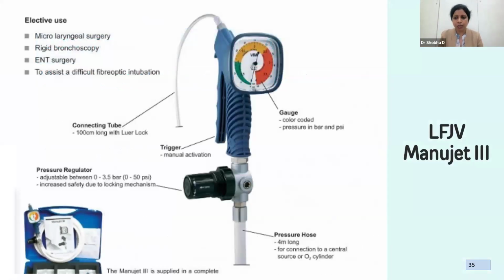So this is the Manujet 3. Some of its parts: it has a connecting tube which is 100 centimeters long with a Luer lock which gets connected to the catheter. We have the trigger for on-off manual activation, the pressure regulator with the locking mechanism, and the gauge which is color coded, green for infants, yellow for children, and red for adults, given in bar and PSI, and a pressure hose which is 4 meters long for connection to the central source or the oxygen cylinder.